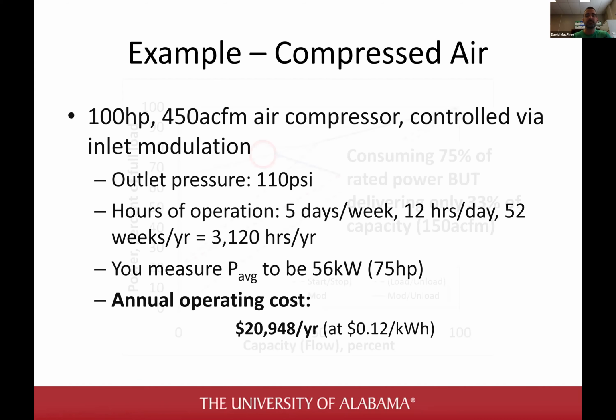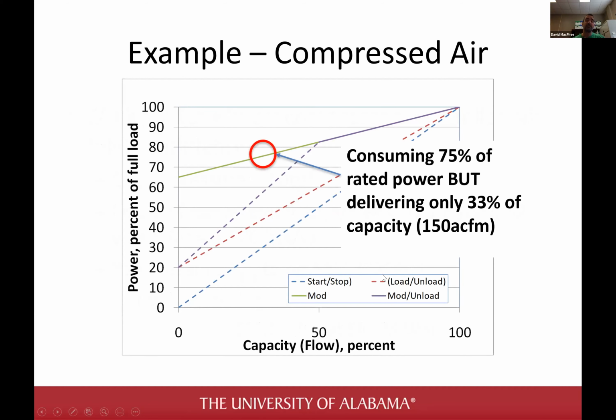But anyway, going back to the performance or characteristic curves, you might be thinking, hey, 75% loaded, yeah, we're doing great. But if it's inlet modulation, consuming 75% of rated power only delivers about 33% of the capacity based on how modulating controls work. Now, there are not a lot of compressors these days that just use pure modulation all the way down to zero flow capacity. A lot of them use modulation with unloading. So they'll modulate down to a certain percentage, and then they'll start going to load, unload, kind of a mix between the two.